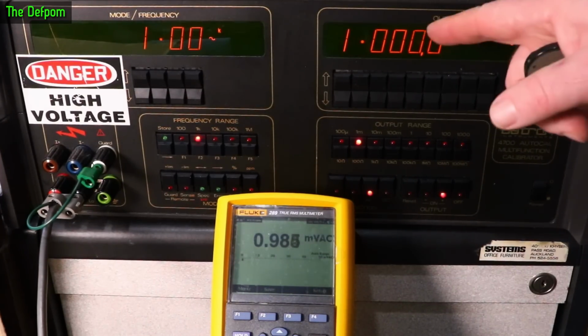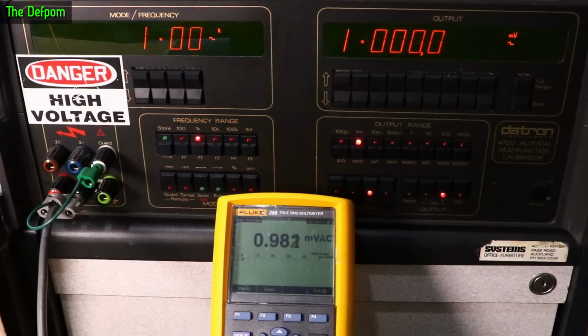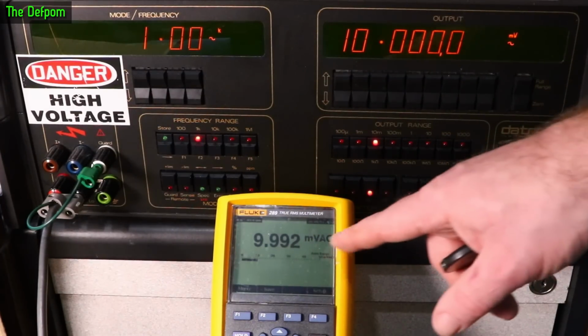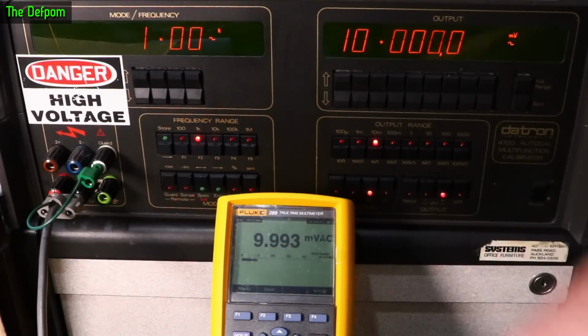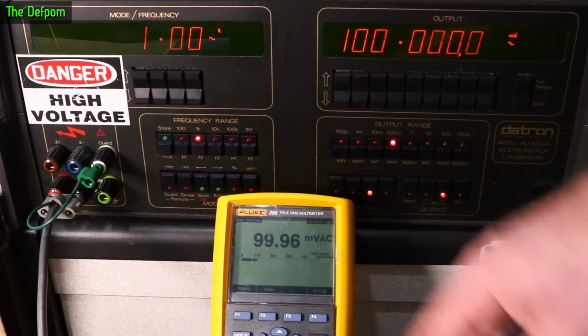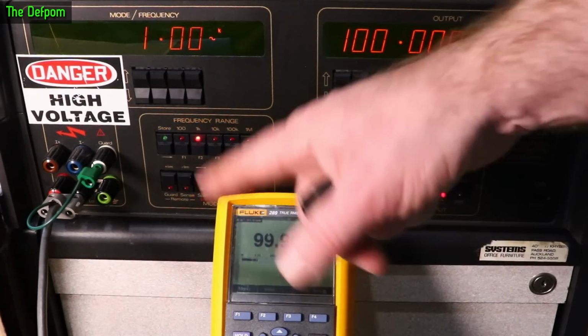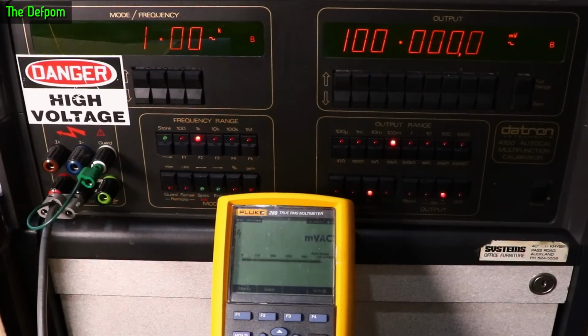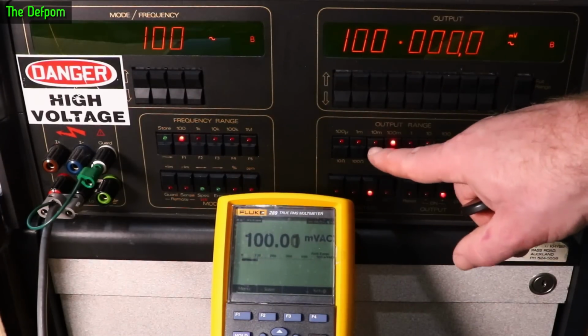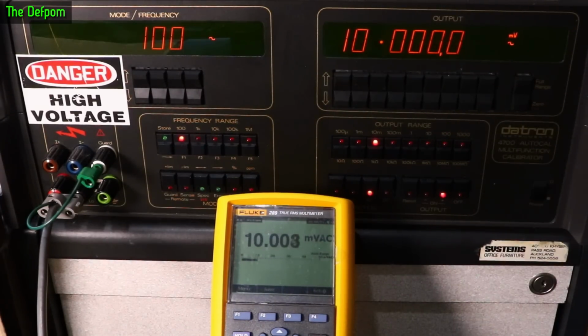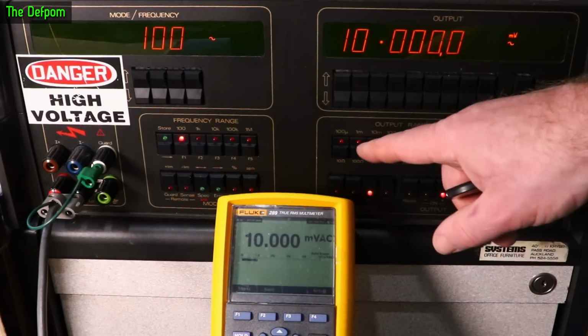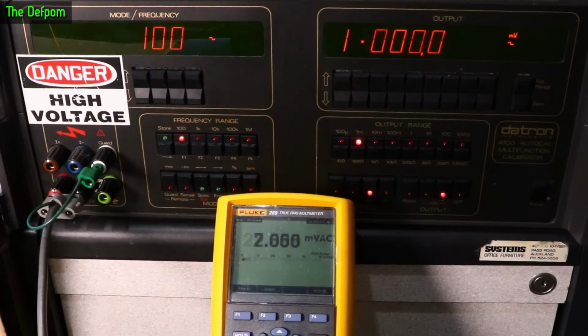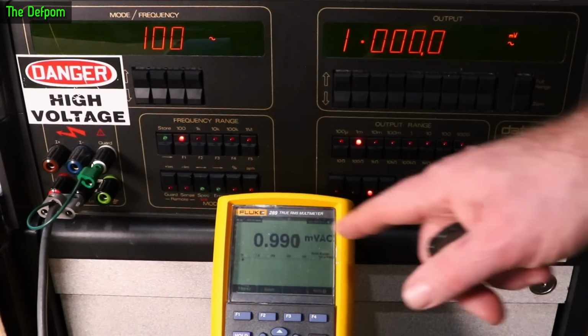So now it's generating 1 millivolt at 1 kilohertz on AC. And we're getting 0.98 again. Sounds familiar, doesn't it? A couple of counts down on the millivolt range. The 10 millivolts is like 1 count down a little bit there. Well, 8 counts down I suppose. 100 millivolts, a couple of counts down. Let's try doing frequency while we're down here. Let's do 100 hertz. 100 hertz is basically perfect at 100 millivolts. Okay, 10 millivolts at 100 hertz is perfect. Okay, so it's a bit of a frequency dependent thing. And 1 millivolt is still reading low.